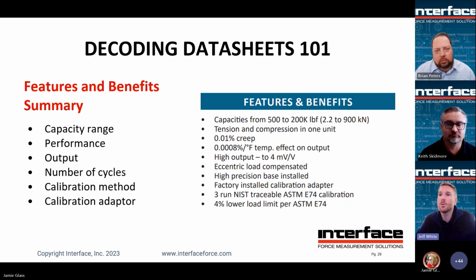Performance. Brian spoke of many of the performance specifications to consider. Be sure to focus on what is important to you and your application. Maybe you're not interested in taking any descending loads, therefore the hysteresis may not be important to you. Creep may or may not be important to you depending on how you are measuring the forces related to your application. Once you start considering eccentric and side loads, you may realize that you're interested or not interested in those values, and maybe a multi-axis load cell is the direction we need to start going down. Are thermal specifications important to you? Would you want to expand the zero compensation range, or adjust the span range as well?